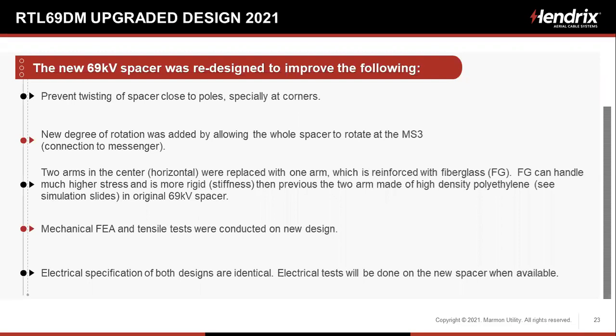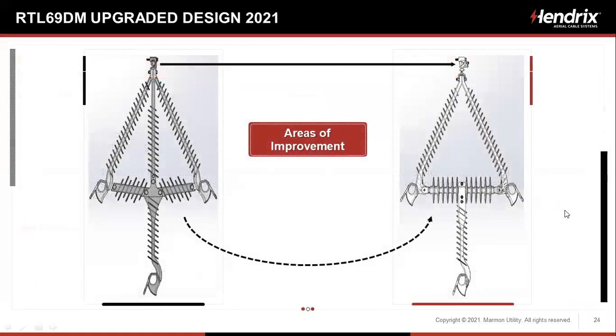So what we did is we added two firm, rigid arms in the center, what we call a horizontal beam. So we replaced those two beams with one beam, which is a reinforced fiberglass. And that fiberglass can handle a much higher stress and is more rigid than the previous two arms. We ran the mechanical finite element analysis and tensile tests to verify that new design from a mechanical standpoint. The electrical specification of both designs is identical. Electrical tests will be done on the new spacer when that comes in, which hopefully is already in.